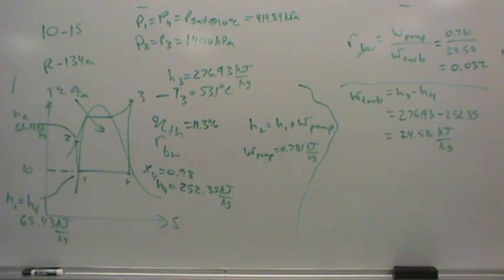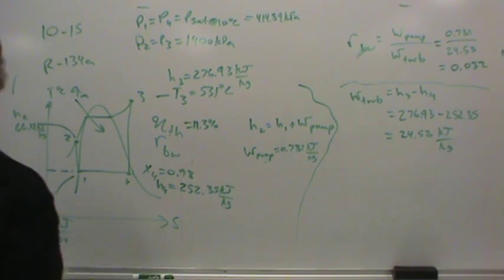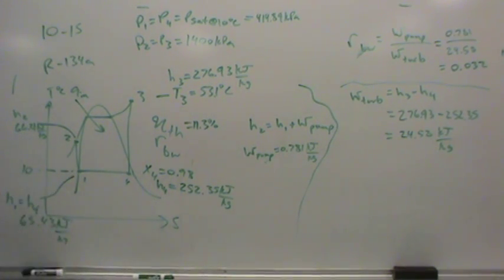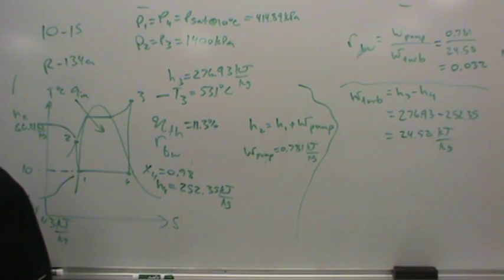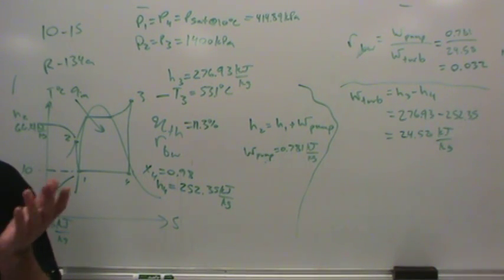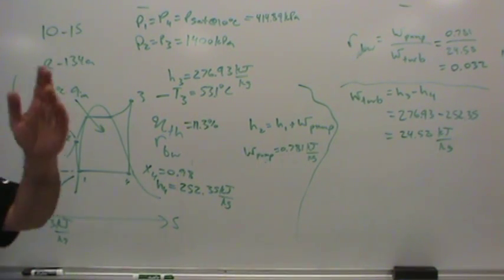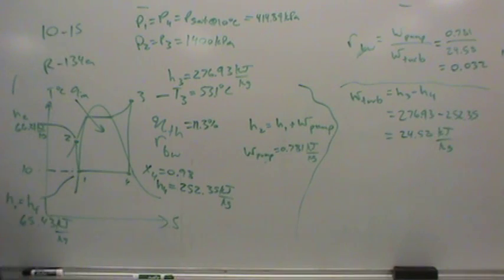That's a pretty good payoff. You can look at this like investment. You invest 78 cents and you get back $25. Tell me where I can find that investment, please. I'd love to do it. So the back work ratio is pretty good on this thing. It's basically the pump work, 0.781 over the turbine work. And so that comes out to 0.032. A little over 3% of the turbines work has to go back into driving the pump. Sounds like a good tradeoff to me. Questions on this problem? What was the key to this problem? When did it really open up? It was all in the states, right? Once we solved for all the enthalpies, everything else was just plug and chug.